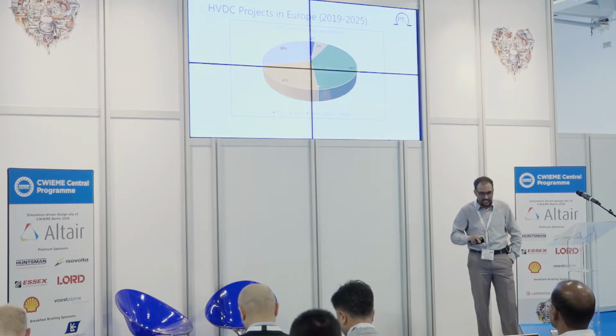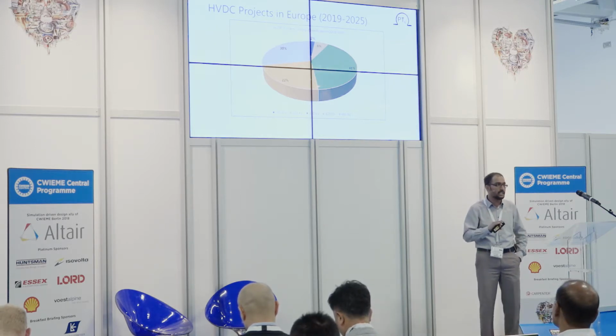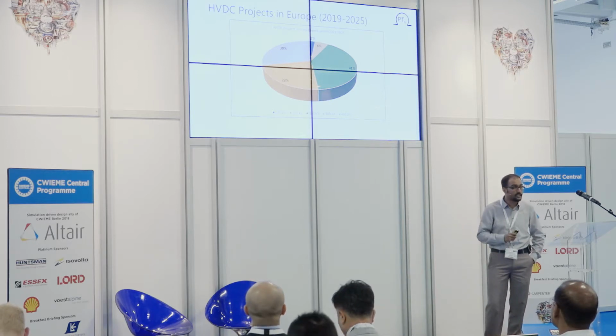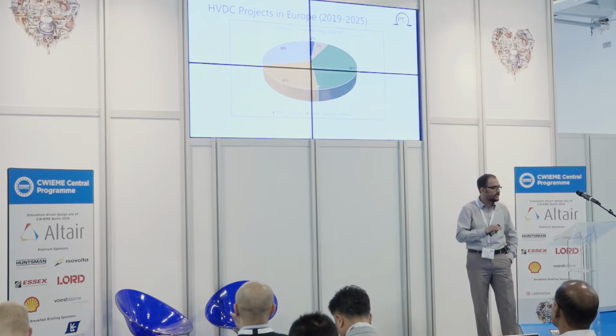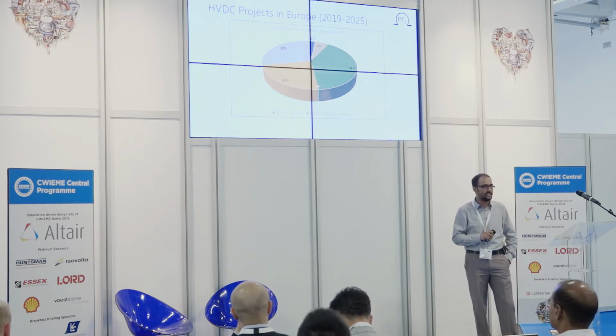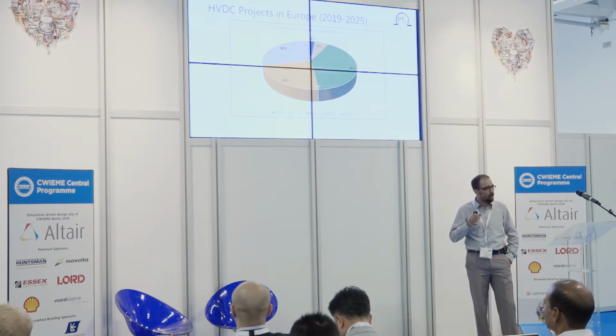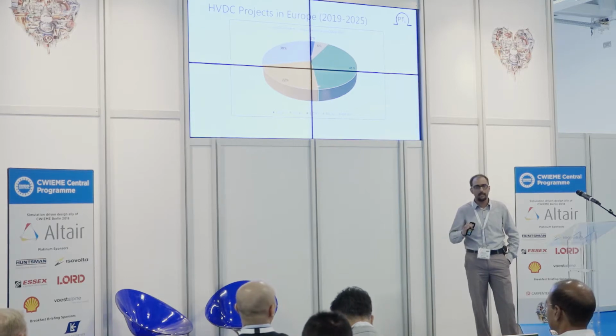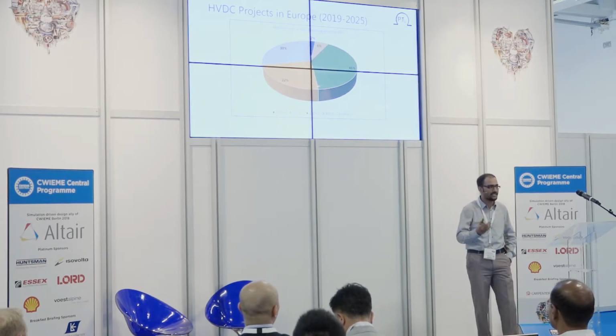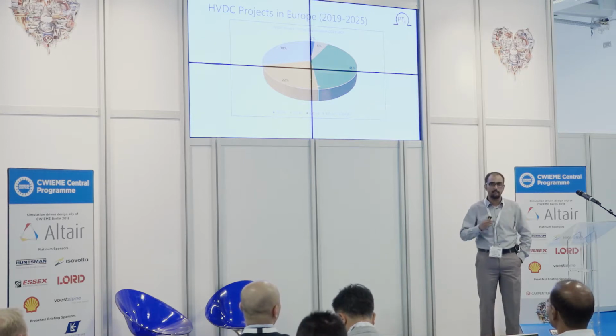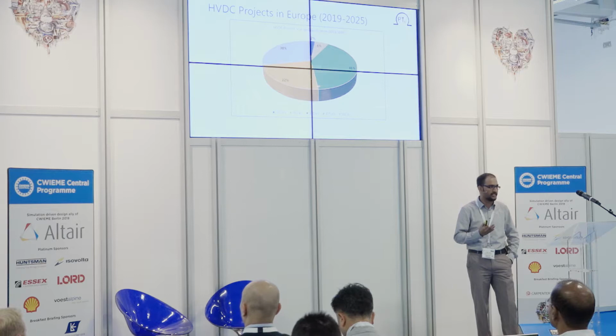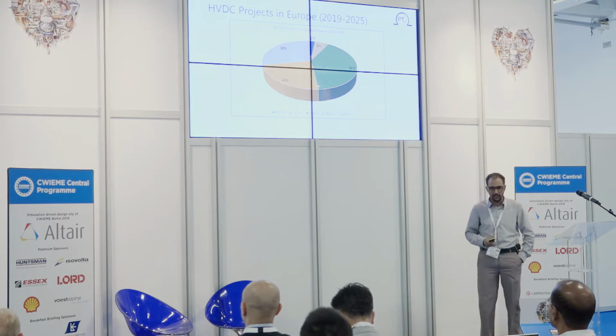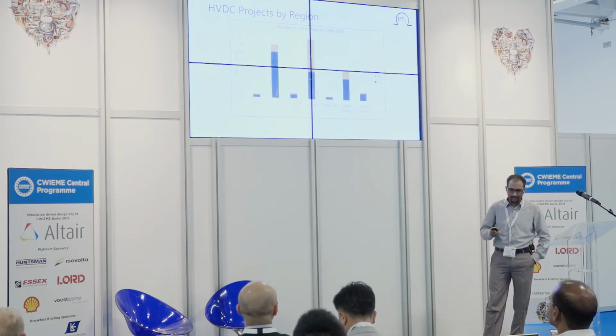Since the projects are planned within these voltage ranges, even though the technology has not been announced by the utilities yet, this tells us that in the European region the focus is going to be the IGBT-based newer technology, which is more flexible and aligns with the grid codes. Since it's more flexible with a smaller footprint, and grid codes have become stricter recently, this technology satisfies those requirements. So this is the global overview of the HVDC scenario.